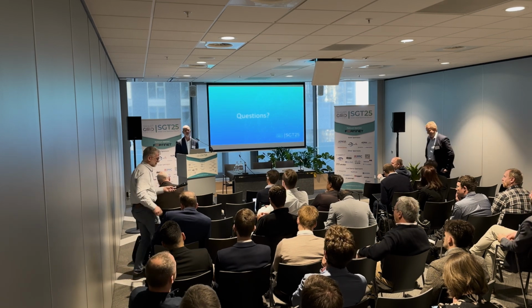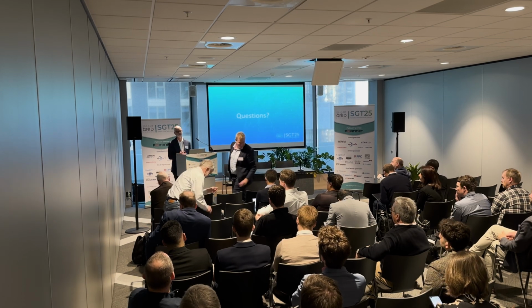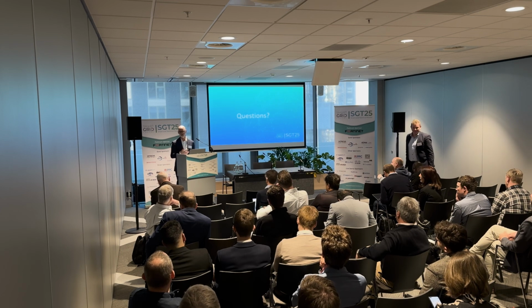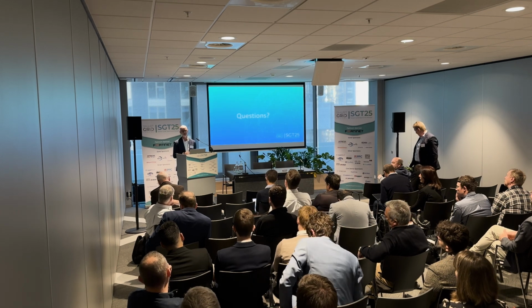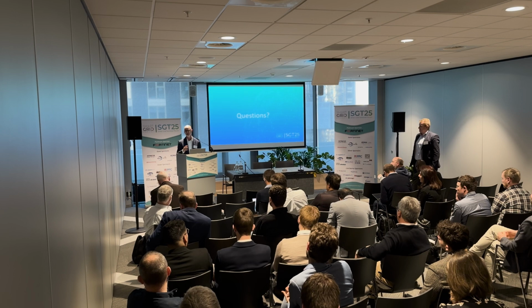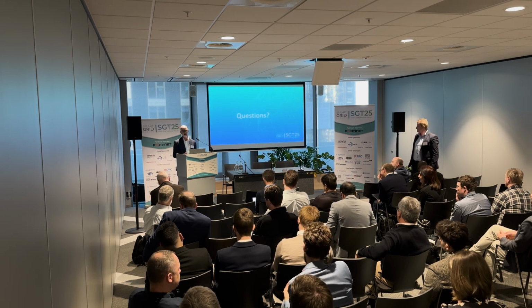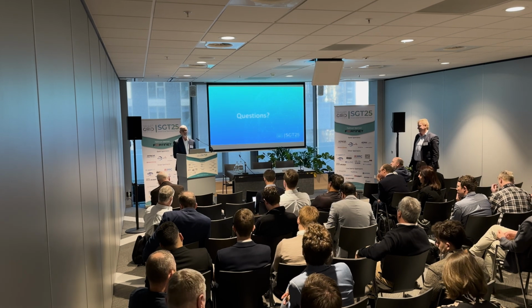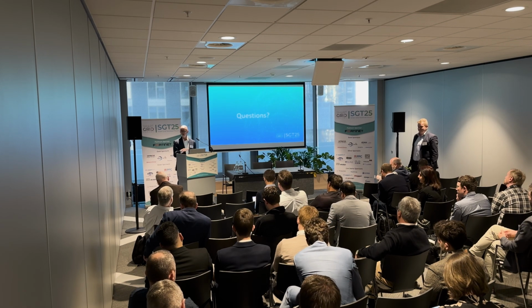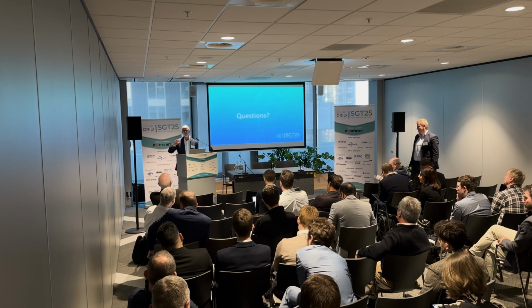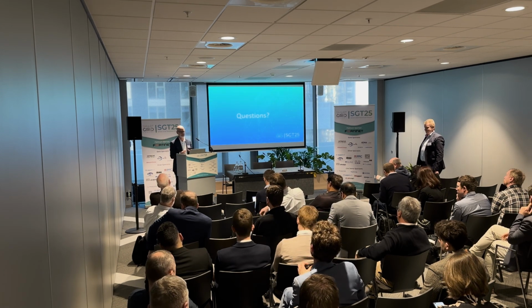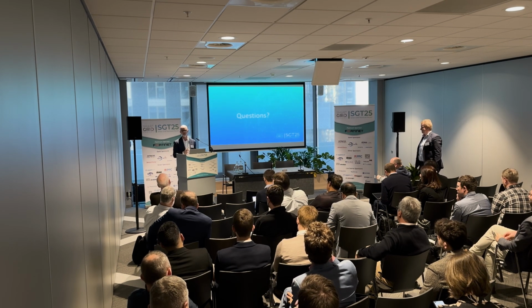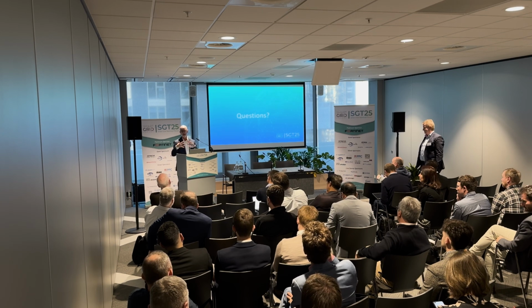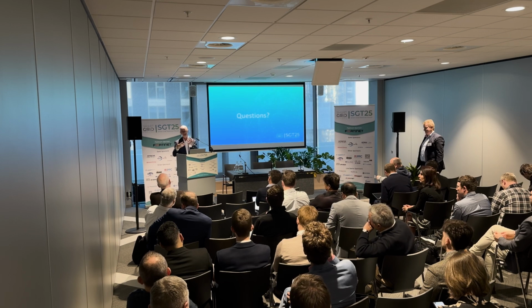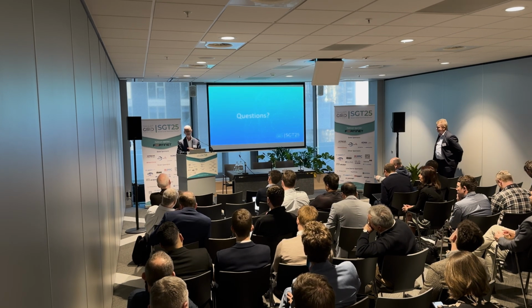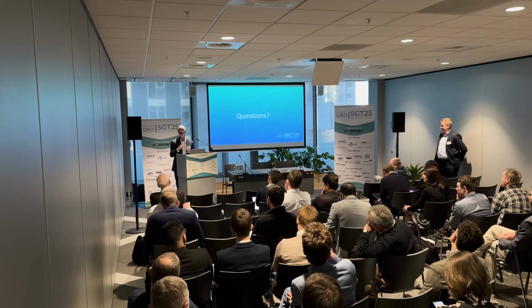What's interesting about how we do stuff internally in our virtual RTU, including our hardware RTU, is that as we bring in data from different protocols, we normalize it into a very basic database internally, so we don't worry about the actual model as much. So when we bring in something like Modbus and then need to send it out as 104 or 61850, by normalizing it in the RTU we just follow the standard on the way out. We can very easily craft and follow any data model of any protocol from any protocol, because mapping something like OPC to 61850 isn't easy. But if you take all that data, make it very flat and basic, you just scale it down and scale it back up—it's very clean that way.